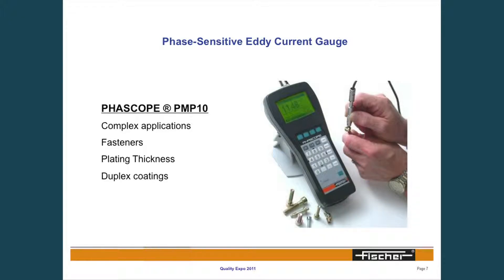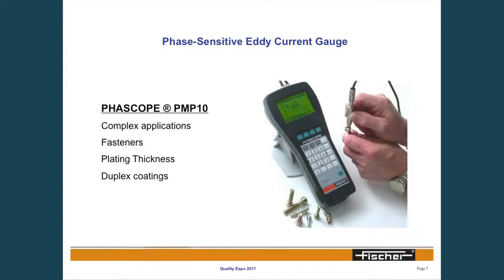There are multiple test methods that can achieve the same goal. For instance, measuring zinc plating — you could use magnetic induction, but it might not be ideal because of the part geometry or size. That's why phase-sensitive eddy current would be the method of choice. The phase-sensitive method is ideally suited for measurements on very small components. It provides excellent repeatability and is designed for measuring zinc plating on fasteners, nuts, bolts, and things of that nature.